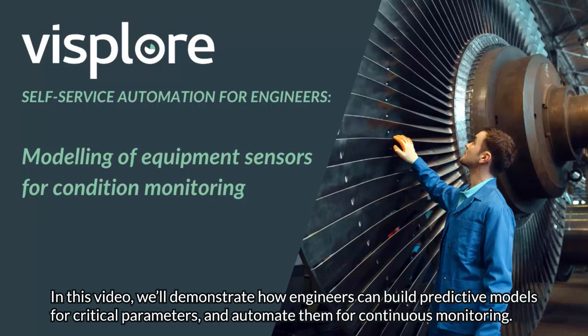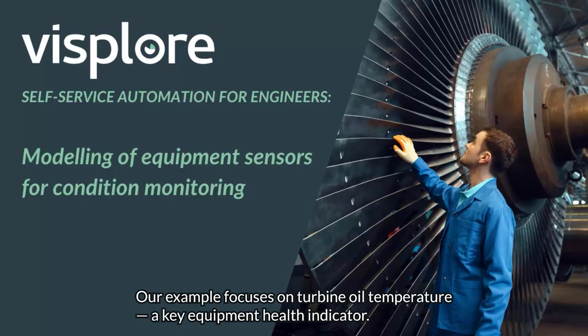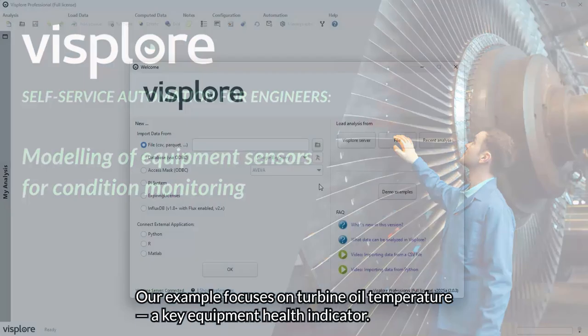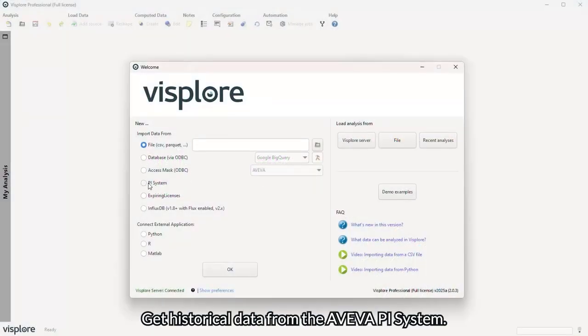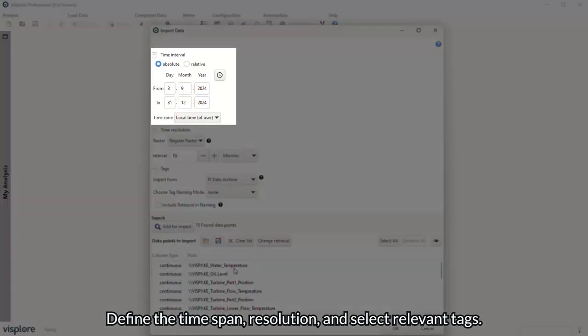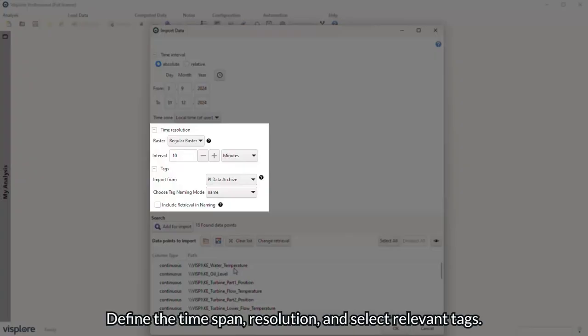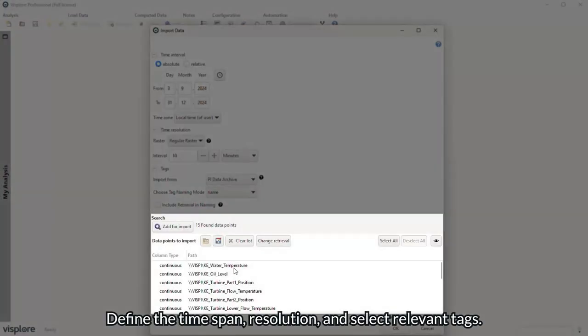In this video, we'll demonstrate how engineers can build predictive models for critical parameters and automate them for continuous monitoring. Our example focuses on oil temperature in a turbine, a key indicator of equipment health. The first step is getting the past operational data from the data source. In this case, the AVEVA PI System. Define the desired time span, temporal resolution, and select relevant tags to import.